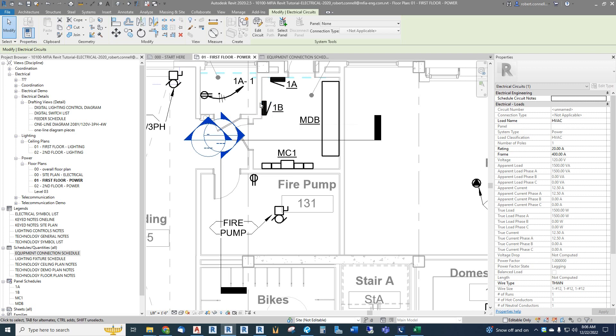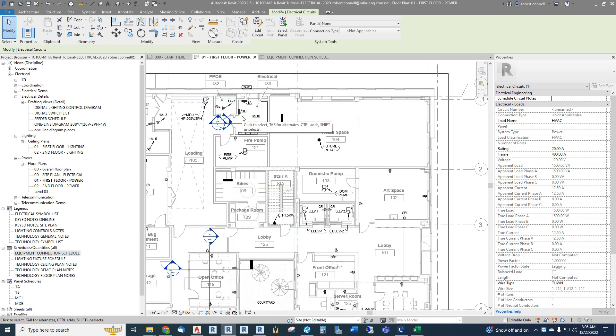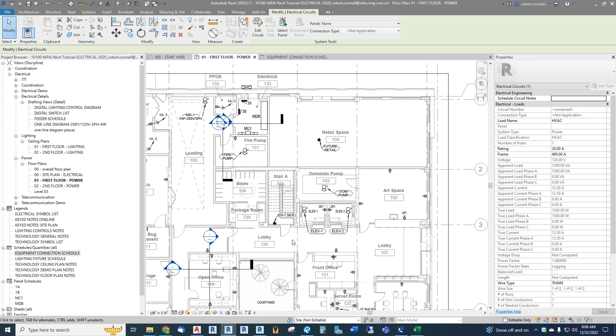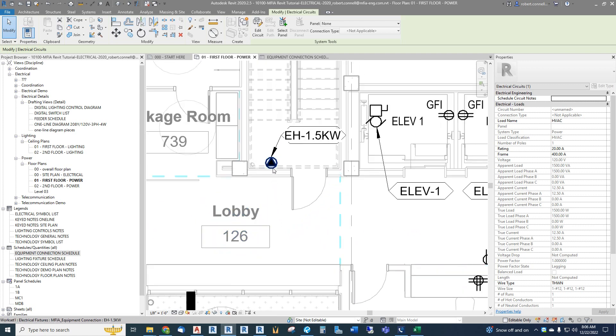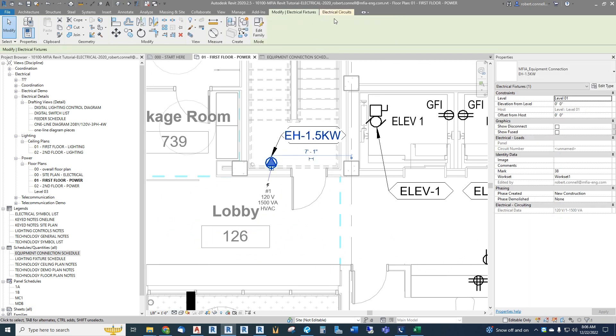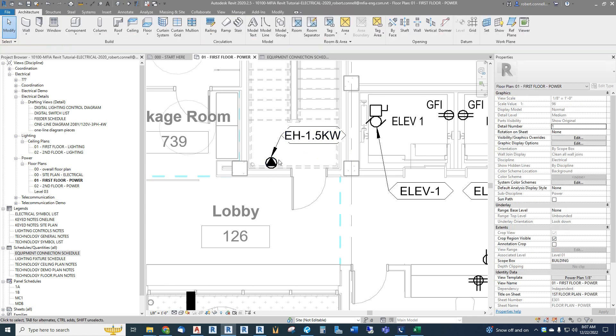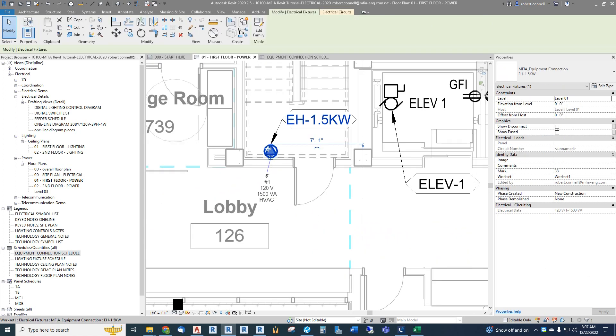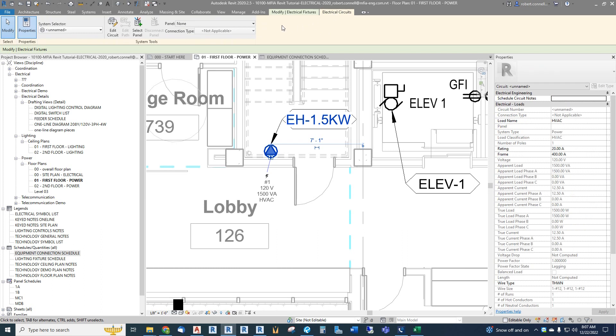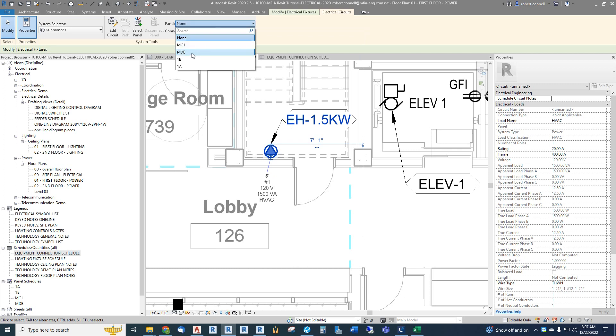That's a design decision outside the scope of this video — there are many considerations, for example ASHRAE metering requirements where you may want to sub-meter HVAC separately from receptacles. Let's say we decided to use panel 1B. If you let go of the power button like I did, you can click back on it — but you won't see the power button because we already hit it once. It went to panel 'none' and got called 'unnamed,' meaning it got circuited but to nothing, so we want to change that to panel 1B.